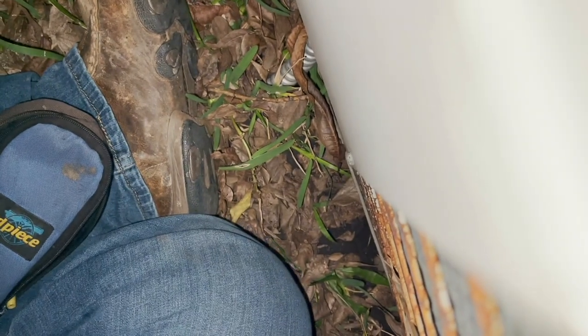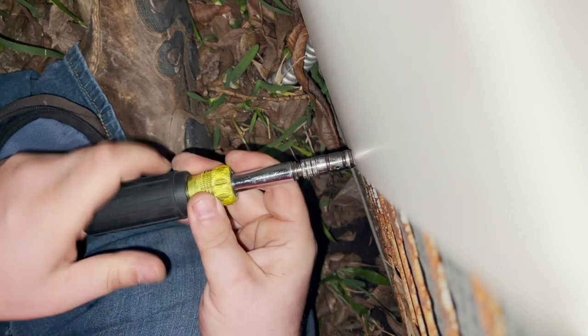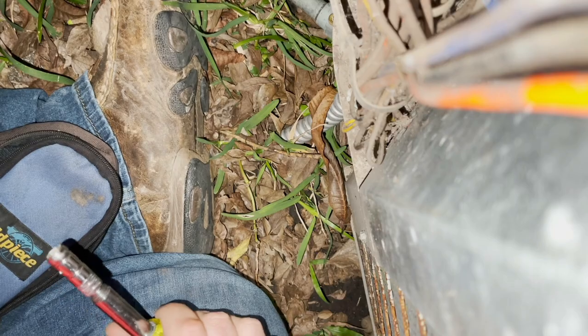This thing is not worth putting a motor on, and plus I think it's extremely low on freon. The indoor coil doesn't look good; the electric furnace doesn't look horrible but it's dirty. I was referred to him by a friend that I put a full mobile home system in for, and we'll probably end up doing the same thing here.